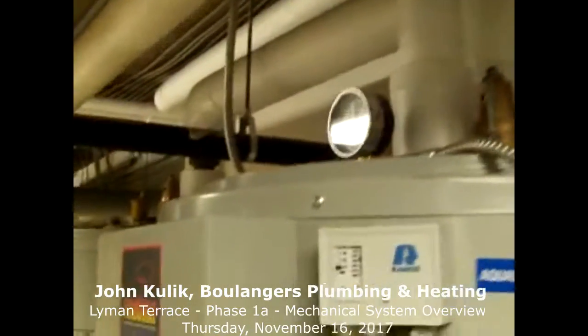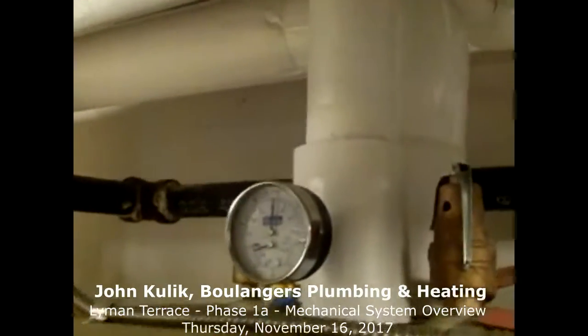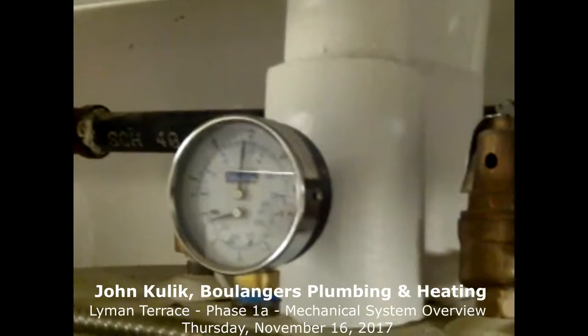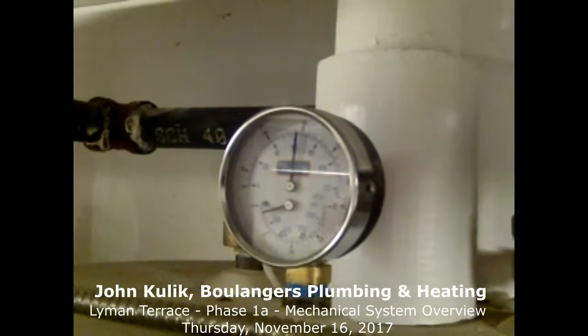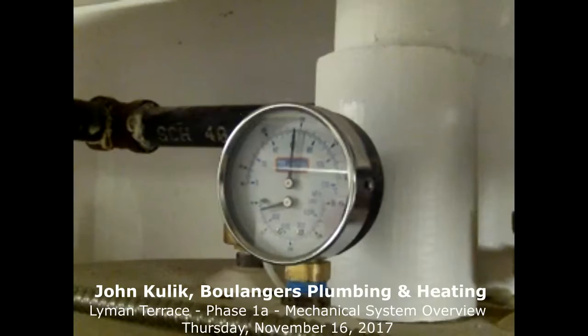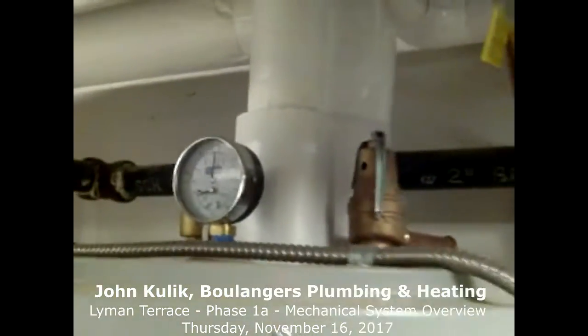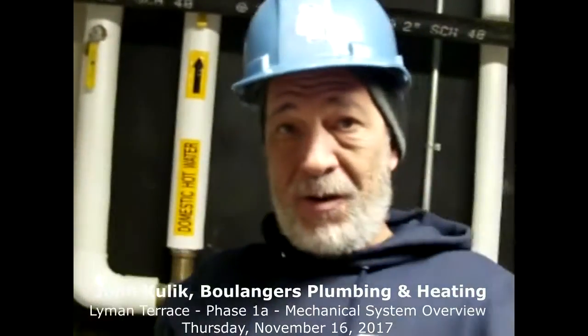There's a gauge on top of the tank for the tank temperature and the water pressure. Only thing is, like I said, the tank stays elevated, so that should be roughly between 140 and 150 at all times. There is a 10-degree differential on the tank. You're going to be up or down 5 degrees on the swing.